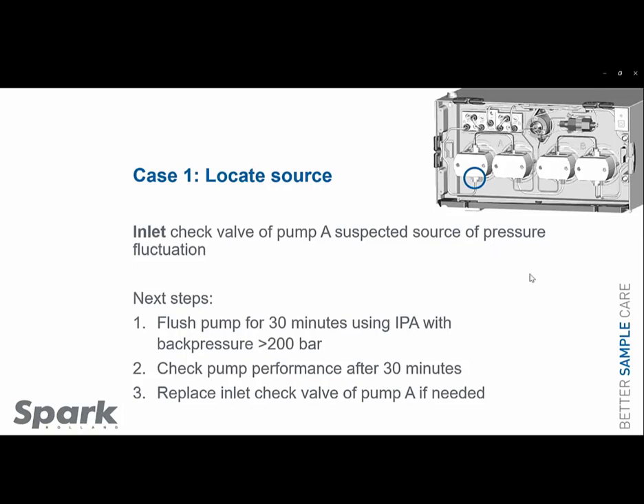Before replacing any parts on the pump, we follow the next steps. We are going to flush the pump for 30 minutes using 100% IPA with a back pressure of at least 200 bars. After that, we will check the pump's performance. If the flushing didn't help, we will replace the inlet check valve of pump A.